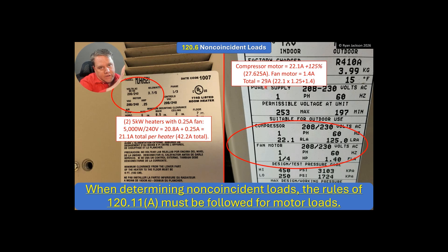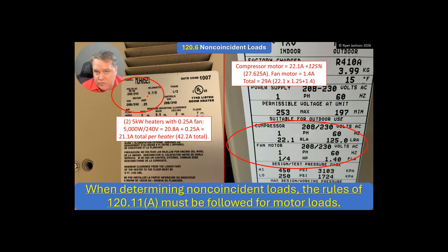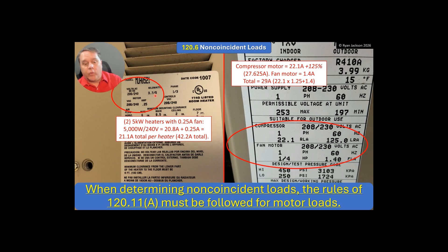Then I'm going to compare that against my heating. I've got two 5kW heaters. Let's say we're doing a feeder circuit right now, so I've got one air conditioner and two heaters. My two 5kW heaters are a resistance load, so 5,000 watts divided by 240 — nice and easy. And it has a very small motor, a quarter of an amp — like an eighth horsepower motor. When you go to 120.11(a), it says for a tiny little motor like that, eighth horsepower or less, just do it at 100%.